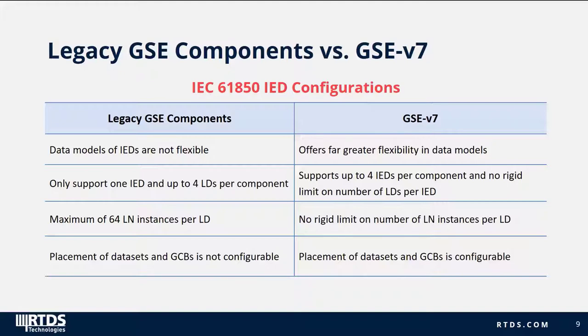In legacy GSE components, placement of datasets and GOOSE control blocks is not configurable, whereas it is far more configurable in GSE V7. The user can create their own datasets by selecting appropriate data objects and data attribute instances from the data model, and then assign created datasets to one or more GOOSE control blocks based on application requirements.